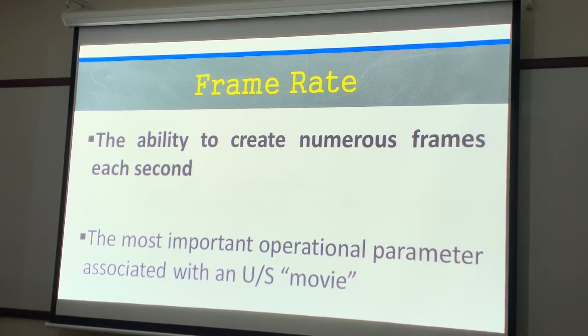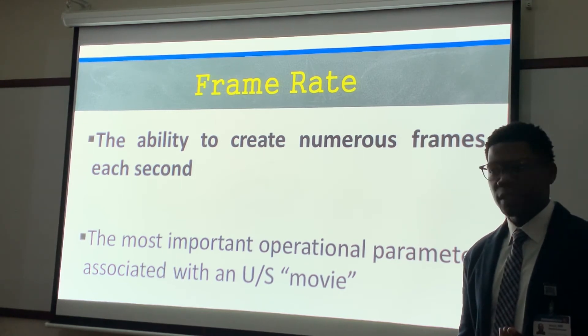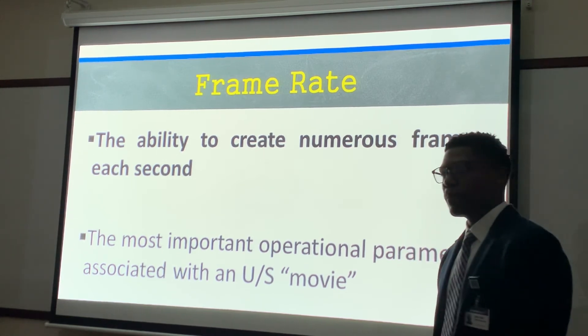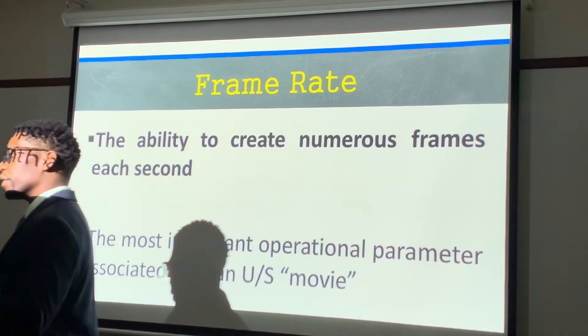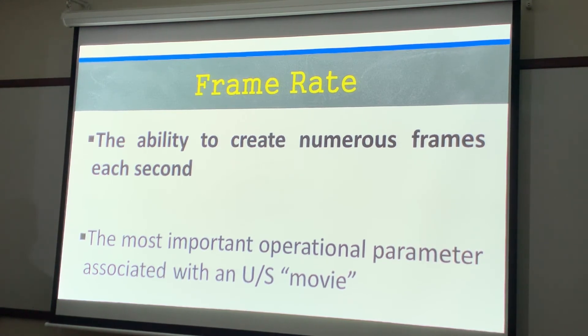Frame rate is the most important operational parameter associated with an ultrasound movie. If you need a movie, frame rate is very important. If you don't need a movie, detail is more important. There's always a trade-off between temporal resolution and detail resolution — lateral resolution. Adding more focal zones increases lateral resolution but decreases temporal resolution because it takes so much more time to create that image.